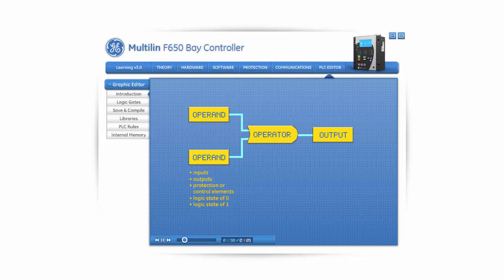The operator can be an OR gate, AND gate, NAND gate, XOR gate, NOT gate, timer, or latch. With the F650, the output flag is called a virtual output within the relay. It can later be used to operate an LED, contact output, or generate an alarm within the relay.